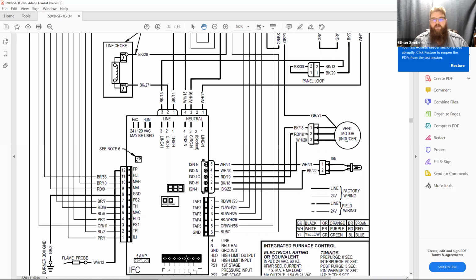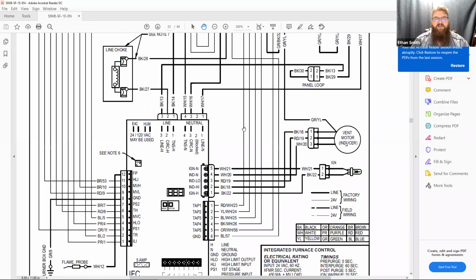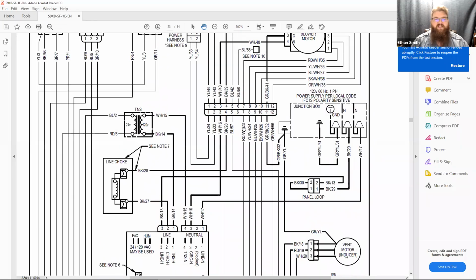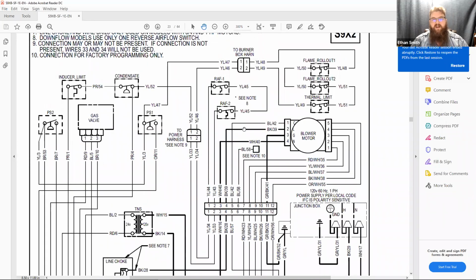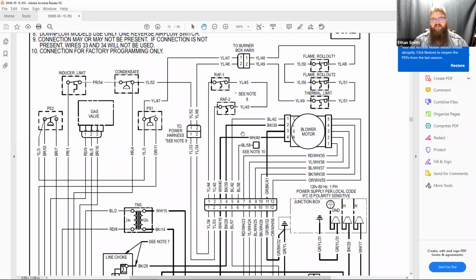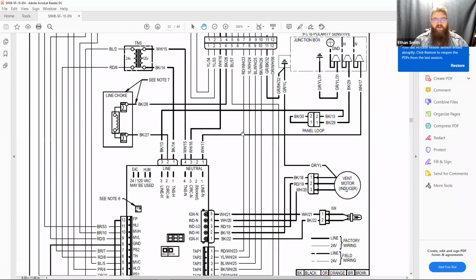So we know that at this point we should be sending line voltage to that inducer motor, and if it's coming out of the board and arriving at the inducer motor, that inducer motor should be running. If it's not, we know that we might have a trouble with the inducer motor. We can then power it down and ohm out the winding on the inducer motor just to confirm that that motor is dead. Okay, so we use the knowledge of sequence of operation in combination with the tools that are built into the wiring diagrams, guys, to trace power. And that's really the name of the game with electrical diagnostics, guys, is knowing how to trace power.